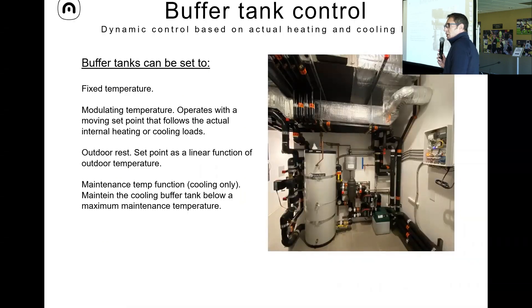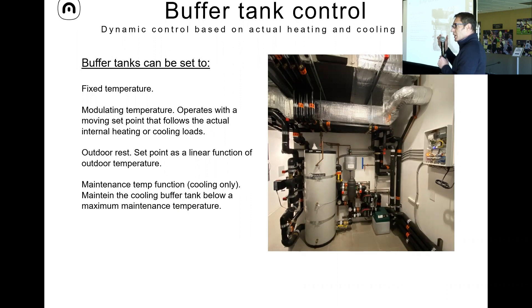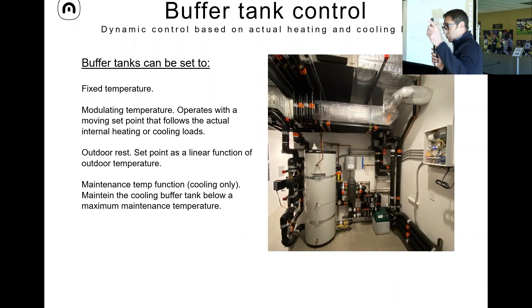One of the most critical items to control with our philosophy is the buffer tank — it's the center of the system. The computer receives all information from the different rooms, and as a consequence, we dictate what the supply temperature should be for the ceiling, the floor, or the fan coil. We then dictate the temperature in the buffer tank, which requests the right temperature from the heat pump or the boiler.